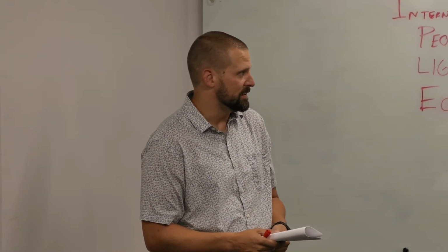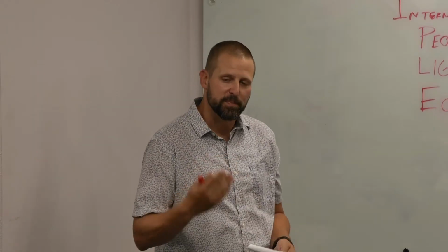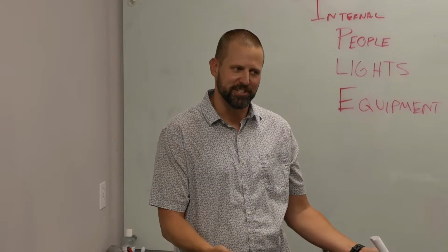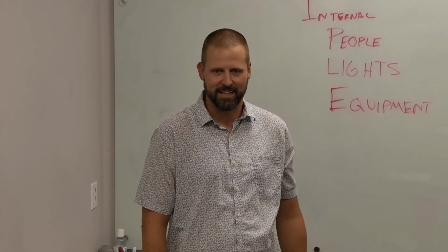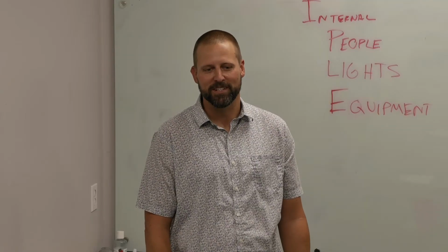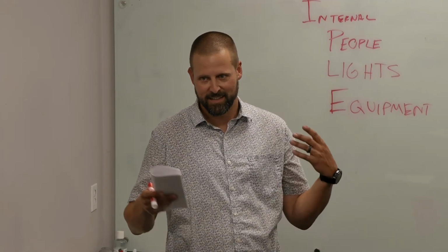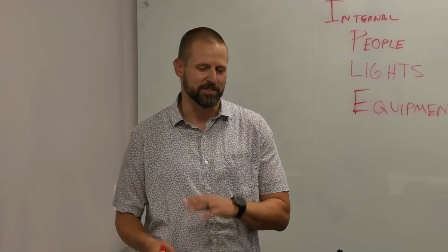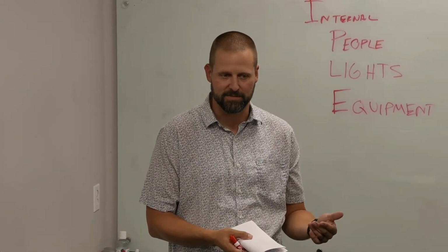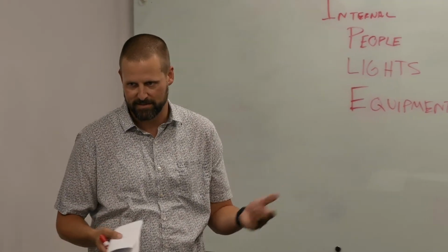So we experience a lot of, oh, this is this type of lab, you're an engineer, you know what that load is, and we'll be like, oh yeah, we know. But no, someone needs to give us point of connections for hoods, which is not a load thing. Someone needs to explain their lab process enough so that we can do heat loads on it.